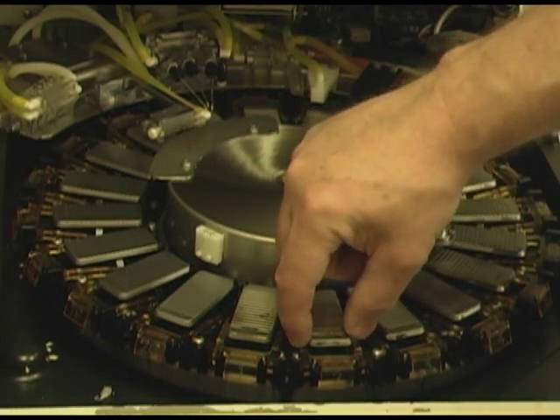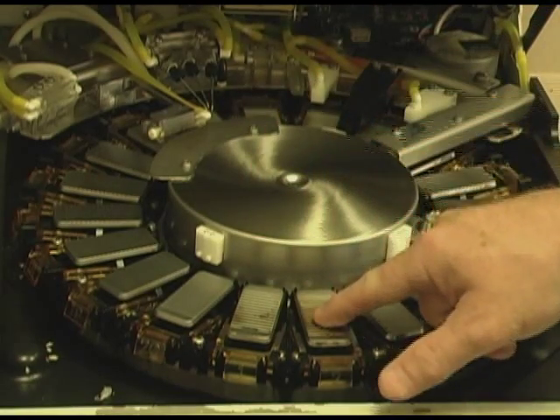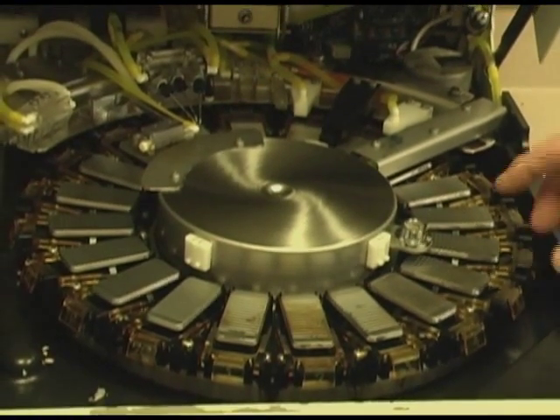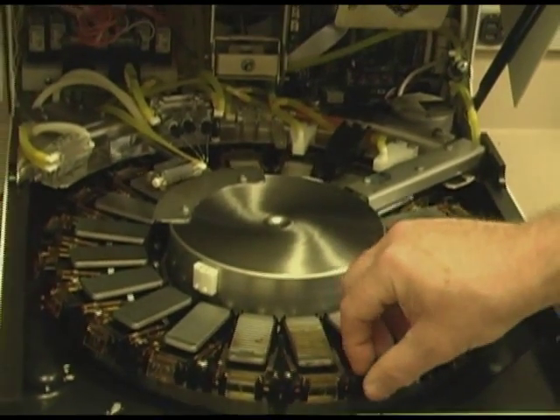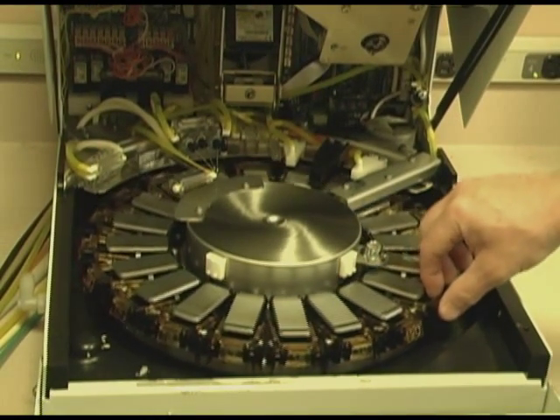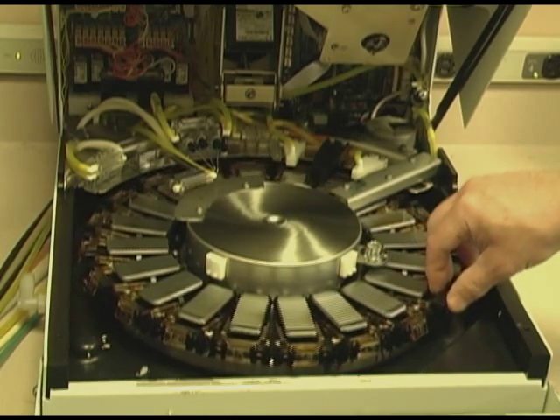These are very easily replaced simply by two screws in the front — take it out and the cable pulls right off. It's pretty straightforward, but the carousel moves the slides into the positions to carry out whatever step is required to get a good stain.